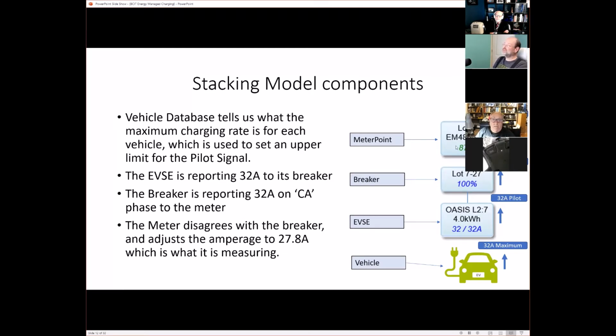This meter point will read the actual consumption of the charging car, and it's saying, you said it was up to 32 amps, but this car is actually only taking 27.8 amps. So that's 87% full. Then, reporting up from that meter point, we were reporting 27.8 and no longer 32 amps. So we can start to get back some of the extra power that we're not actually using in the car charging.